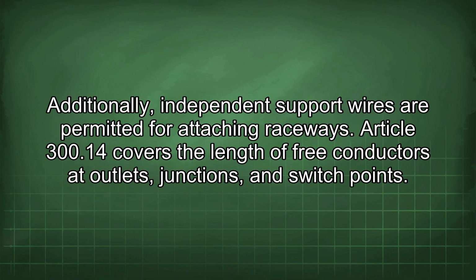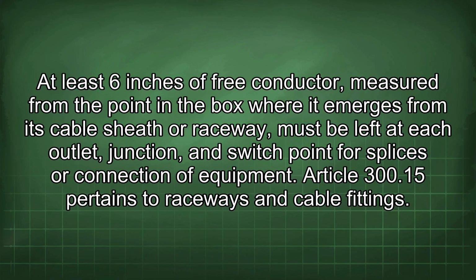Article 300.14 covers the length of free conductors at outlets, junctions, and switch points. At least 6 inches of free conductor, measured from the point in the box where it emerges from its cable sheath or raceway, must be left at each outlet, junction, and switch point for splices or connection of equipment.